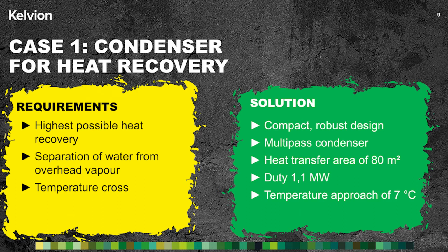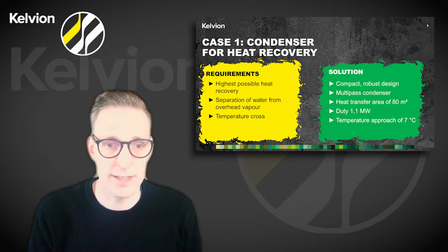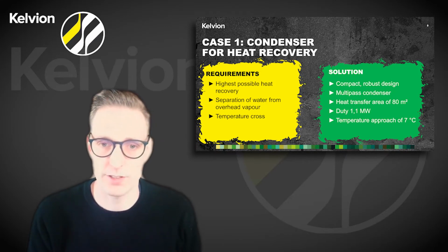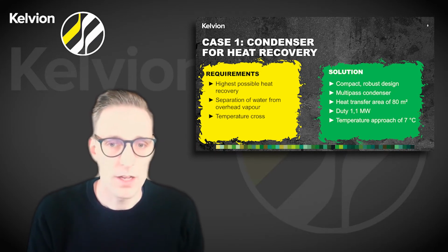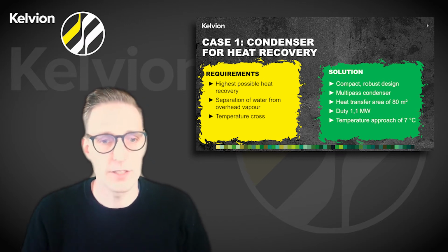For the design, a temperature cross had to be considered. The solution is a K-BLOC in a robust and compact design. To achieve the process parameters of 1.1 MW duty with a 6 to 7 degrees temperature approach, with temperature cross at the same time, it was necessary to design the unit as a vertical multipass condenser. It has now roughly 80 square meters of heat transfer area.